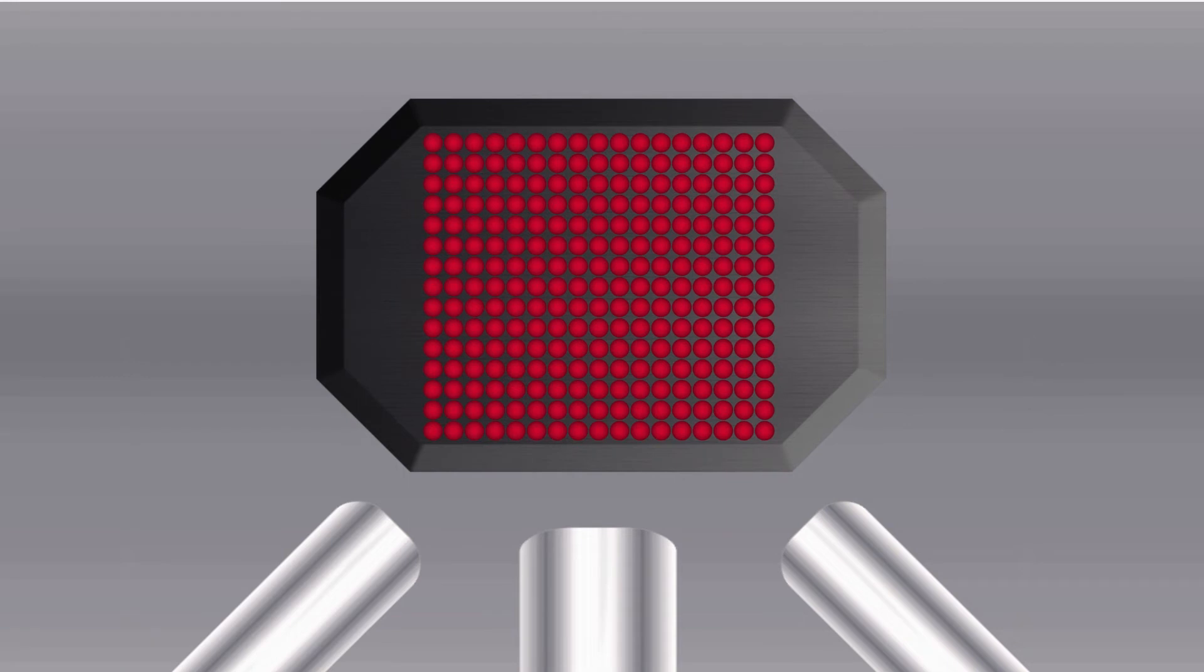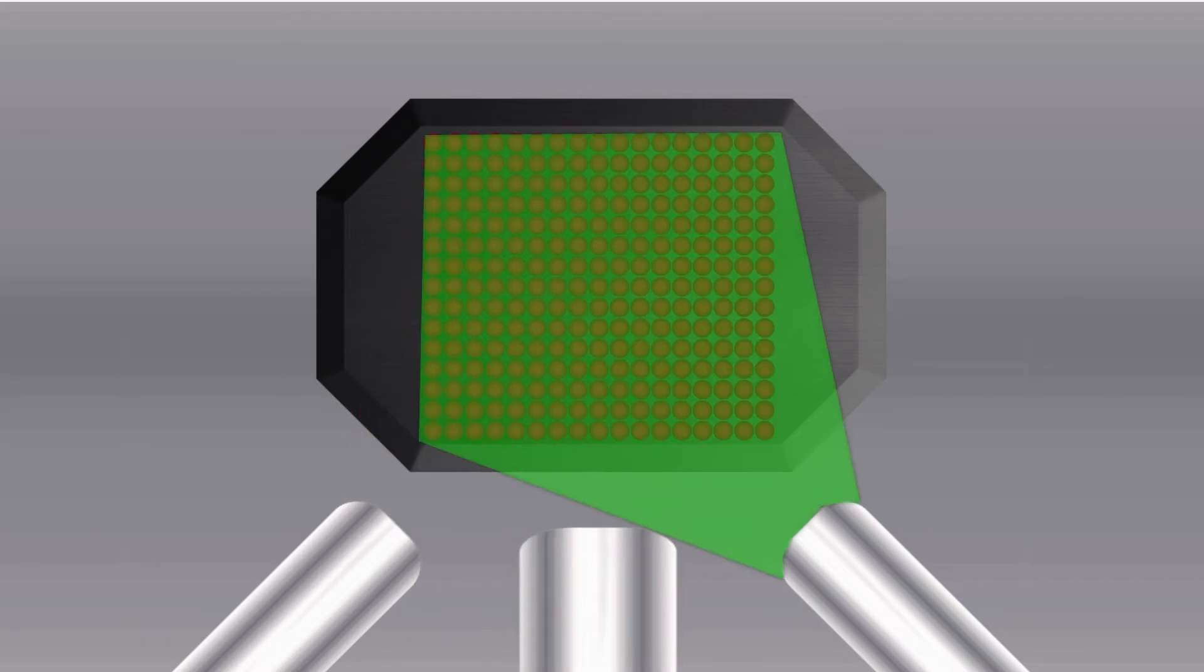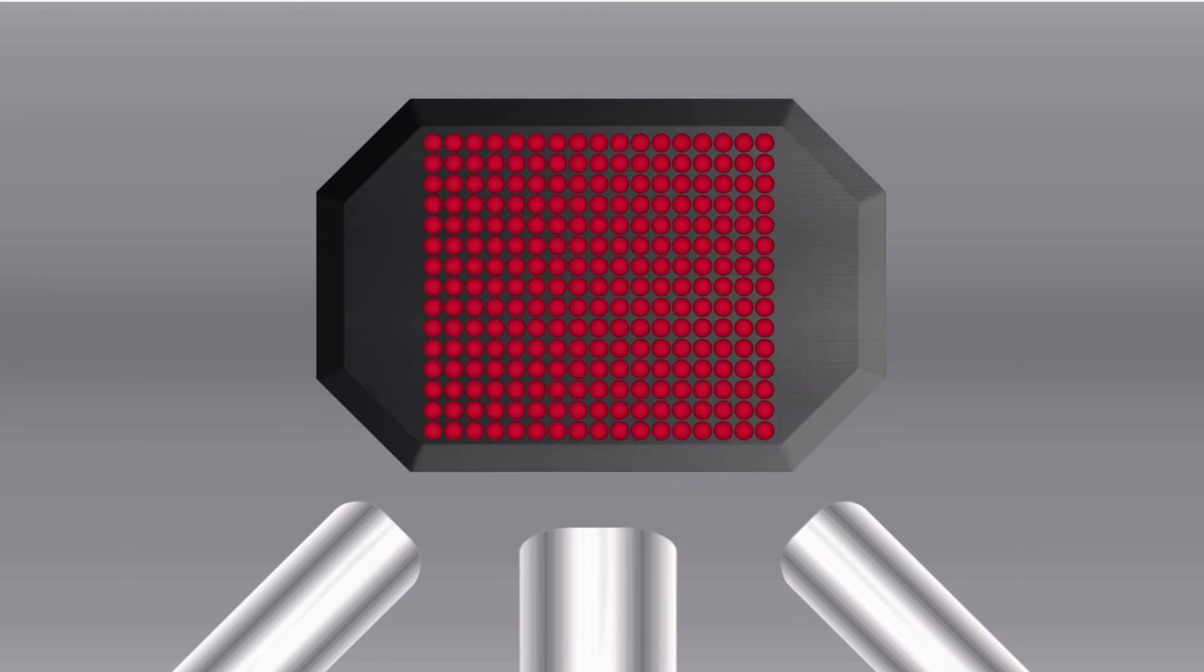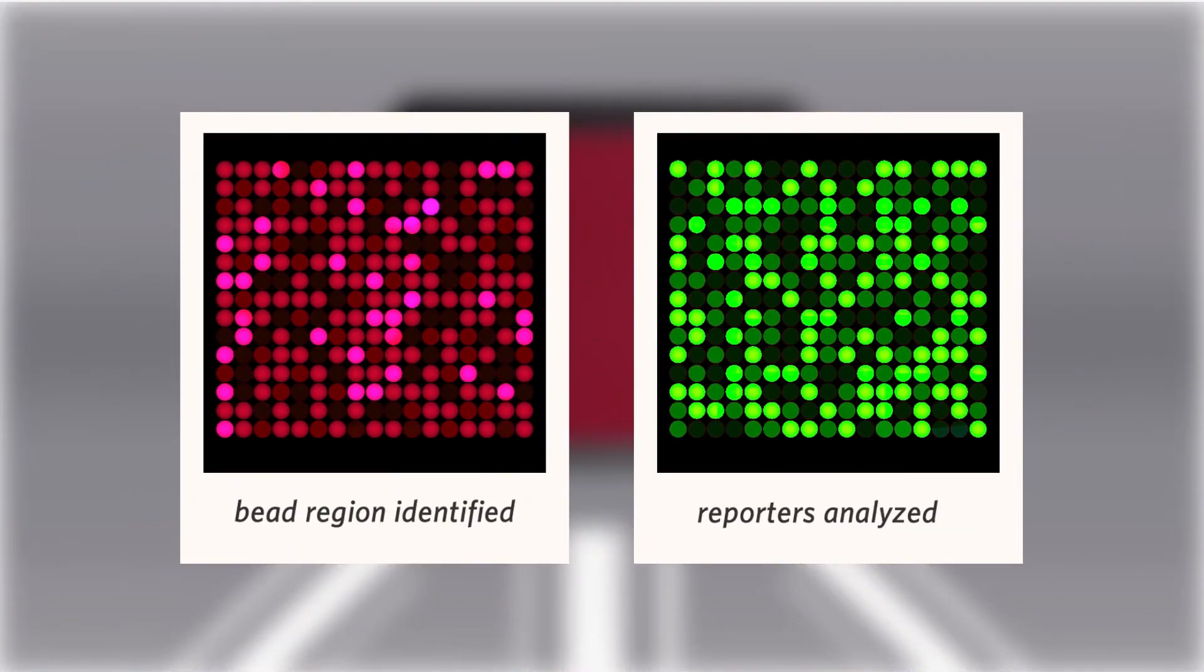Once the beads are in place, a red 635 nm and a green 525 nm LED shine on the beads to excite the dyes and reporter. Then, a CCD camera is used to identify each bead region as well as quantify the analyte binding events.